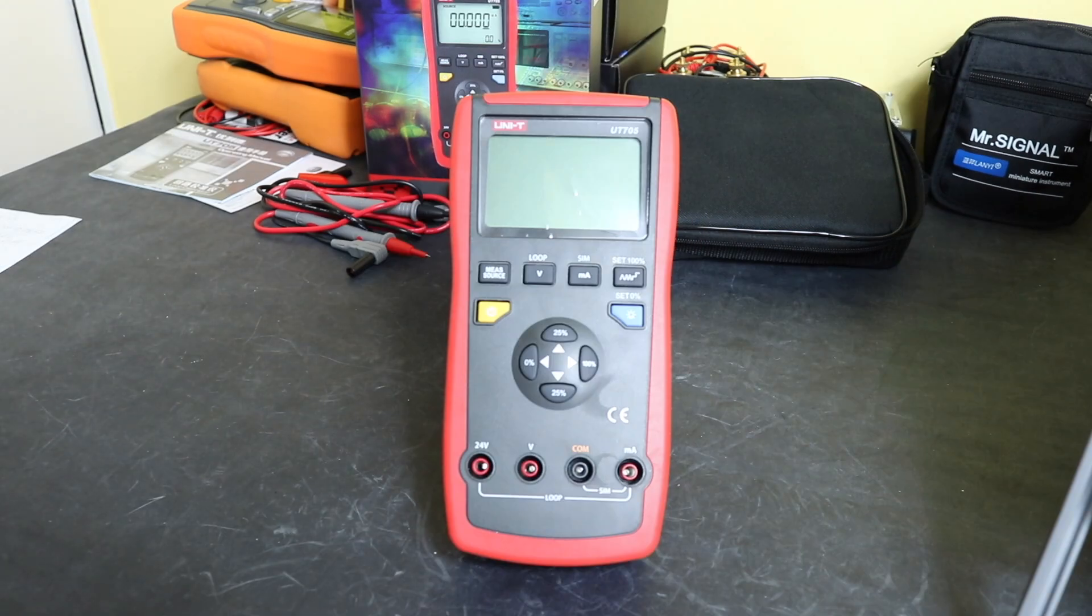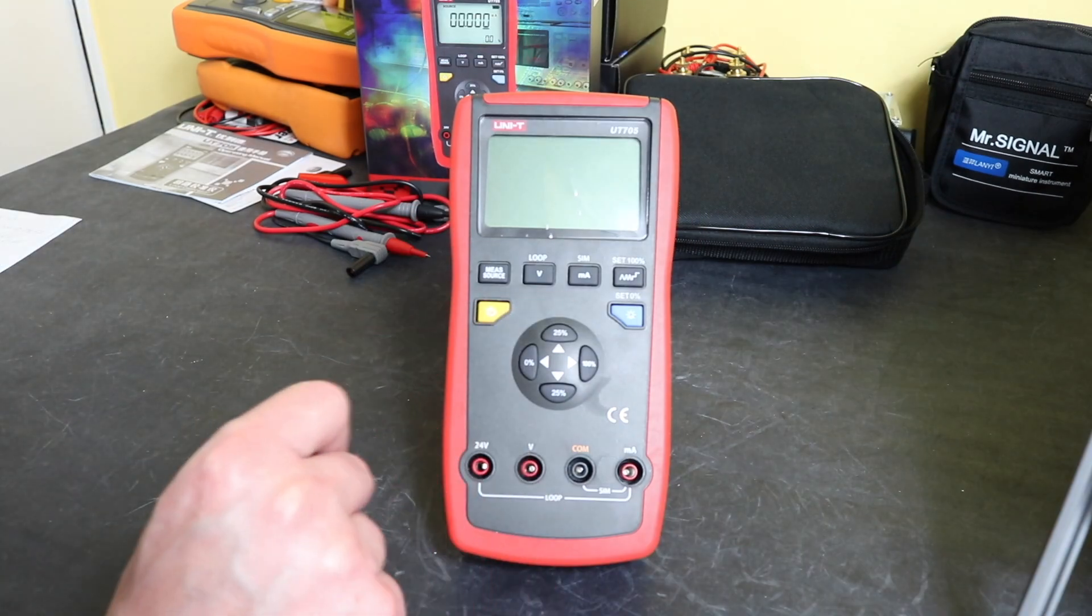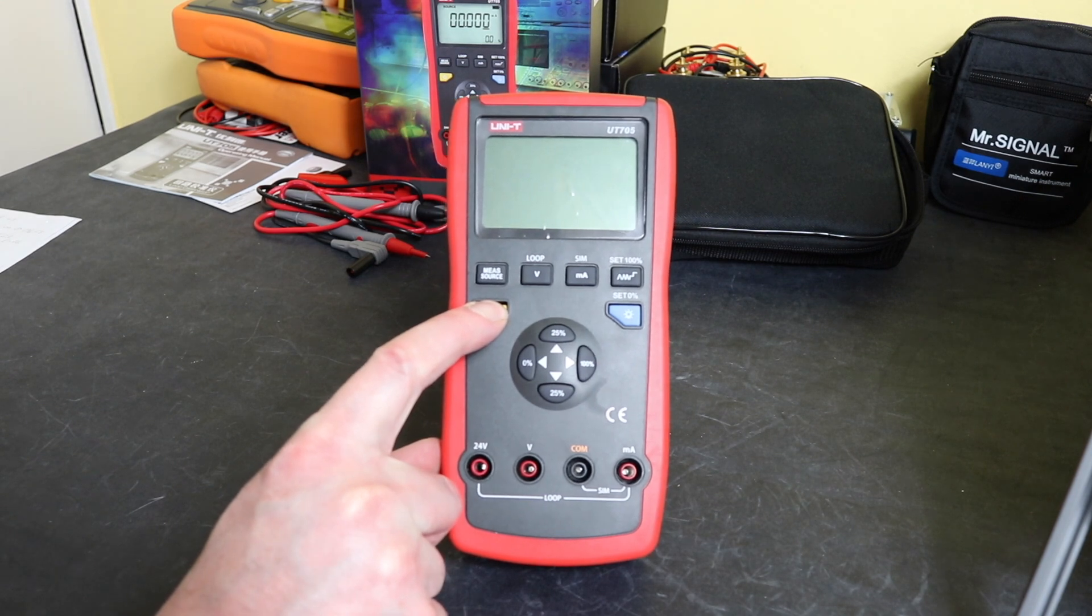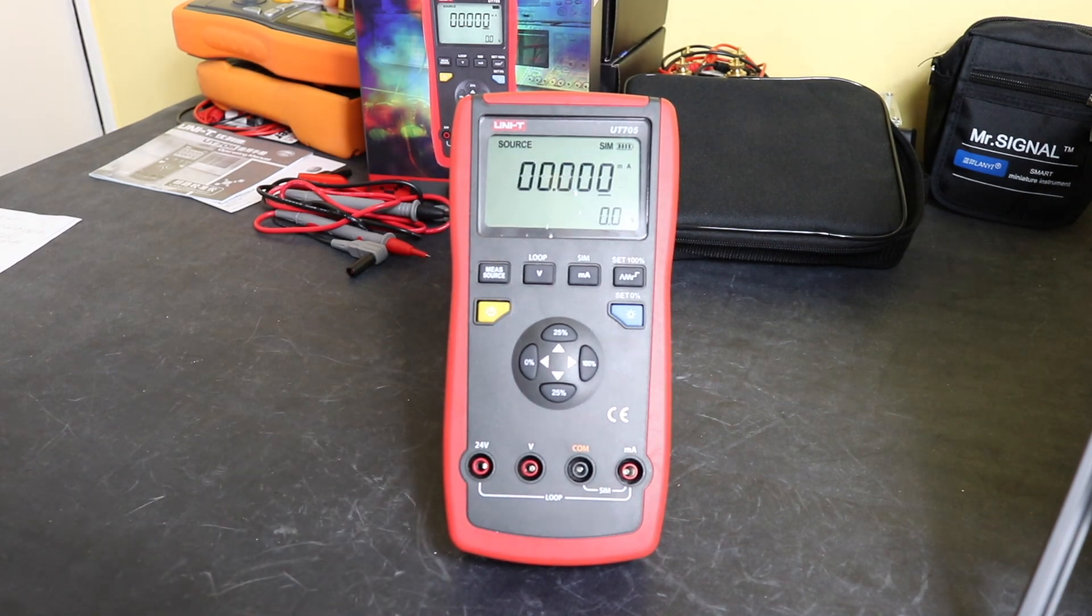We'll take a look at the instrument itself. We have an on-off button on this side here. Now this unit will source and measure current from 0 to 24 milliamps in 1 microamp resolution, and it will measure 0 to 31 volts in millivolt resolution. But it will not source voltage. So unlike all the other process calibrators that I've purchased up till now, all of them have the capability to source and measure both current and voltage, so this is lacking a little bit in that department.